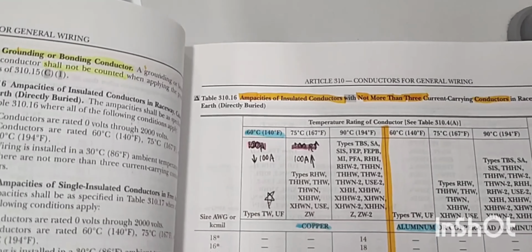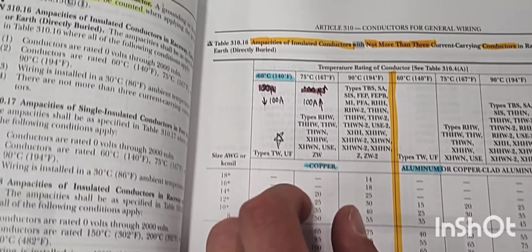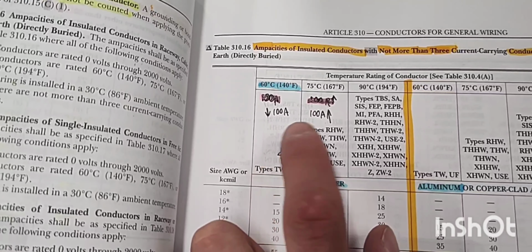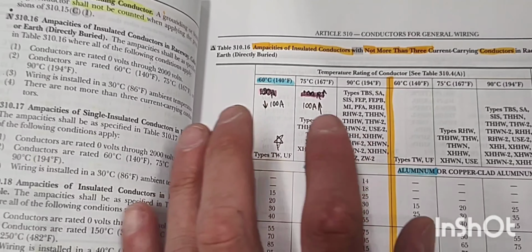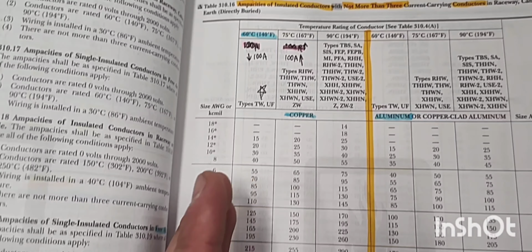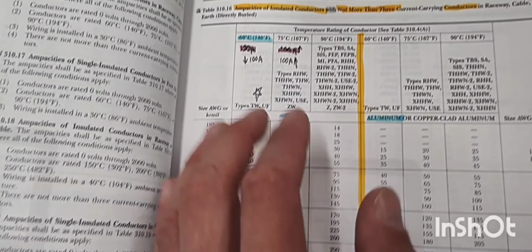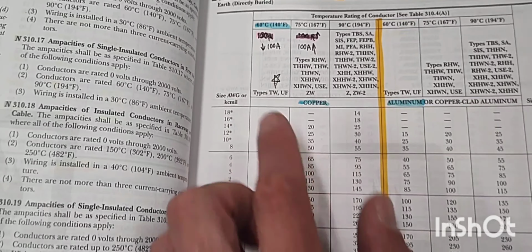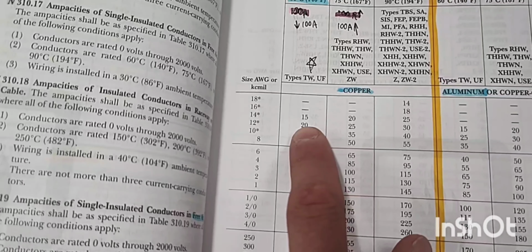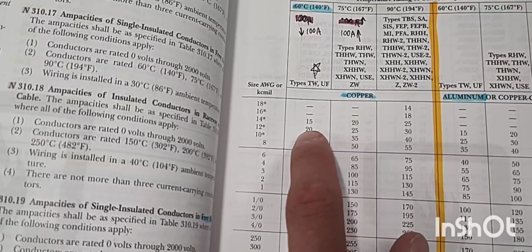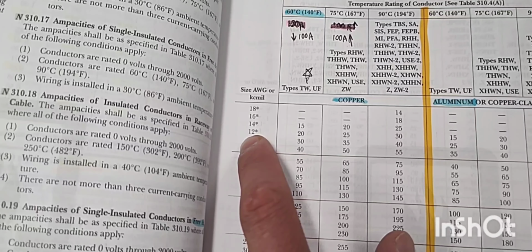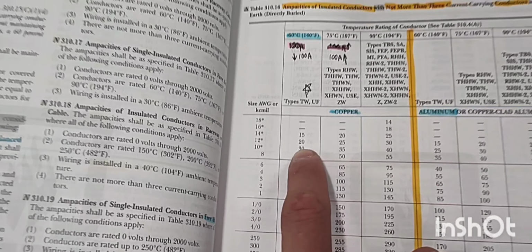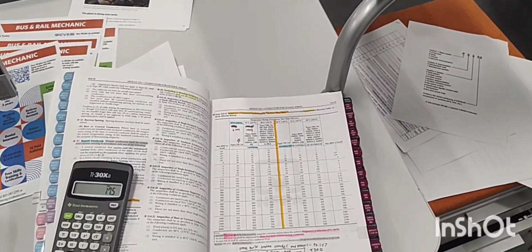Now, let's go into table 310.16, ampacities of conductors. If you see here, I have below 100 amps and above 100 amps. This is just for motor conductor sizing. You shouldn't really write in your code book like that. I just have a little note here for myself. It's below 100 amps, 17.5. So we're going to size up to 20. That's 12s. So we can use 12 wire on this motor.